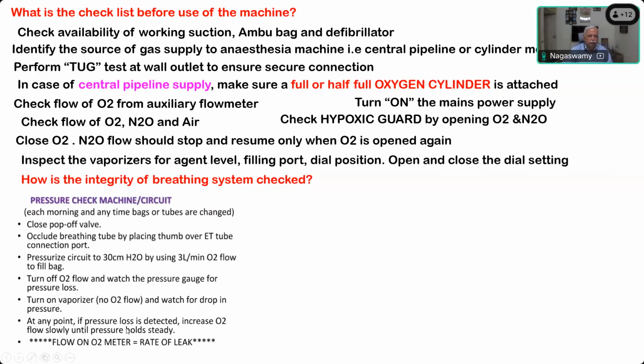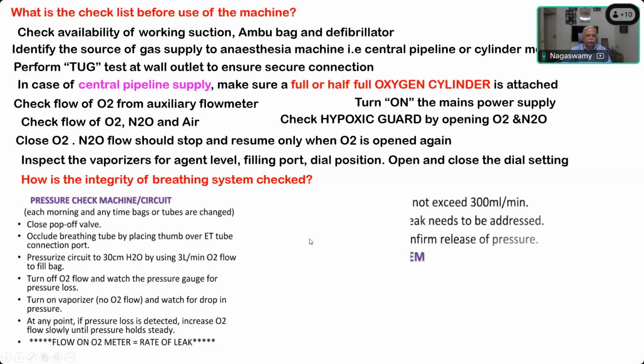So at any point, if pressure loss is detected, increase oxygen flow slowly until the pressure level goes to 30 centimeters of water. And this will now tell you what amount of oxygen flow has happened, that is the rate of leak. For example, if the leak is about 400 ml, 500 ml, and your oxygen flow is kept at 500 ml per minute, and if it is maintaining a pressure of 30 centimeters, that means there is a leak of 500 ml. So flow on the oxygen meter is equal to the rate of leak. This is how the whole thing has to be done.